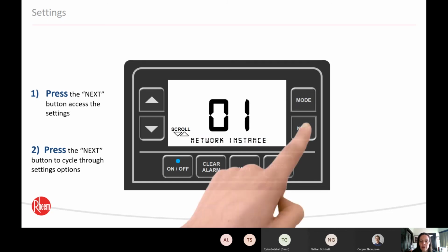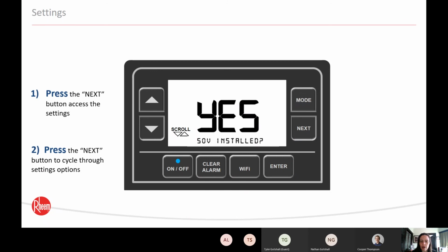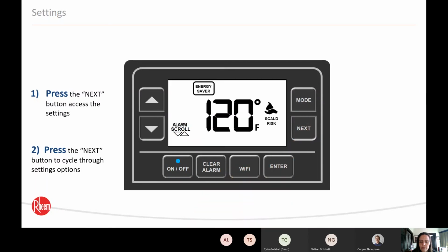But we talked about, if you remember, that middle grade ProTerra product where you can add an auto shut off to it. It's really important if you're adding that shut off kit that you go in - if this was out of the box, it was going to say no because it doesn't have a shut off valve installed. If you add that on, you need to go in, select yes, and hit enter, and that lets the water heater know there is now an auto shut off valve installed with it. So just keep that in mind.